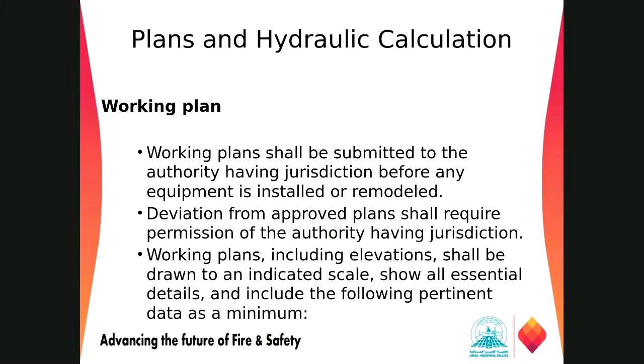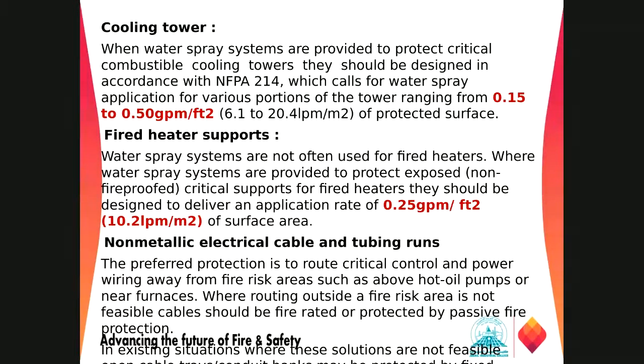Okay, this is all for the cooling tower. Yes, the most critical point is when the cooling tower structure is made from combustible material. It is more common. The cooling tower is constructed from combustible material, and the main concern, because I faced this one earlier, is not when the cooling tower is running, but when the cooling tower is under maintenance and it is empty, dry without any water.